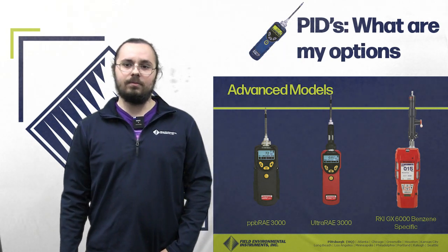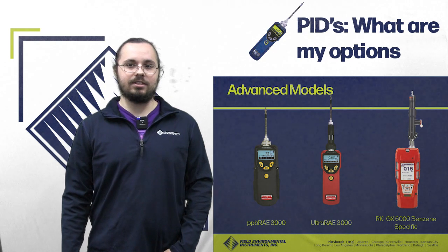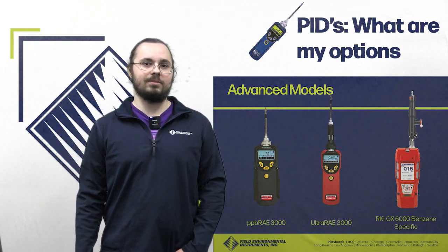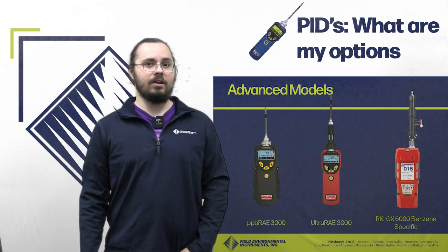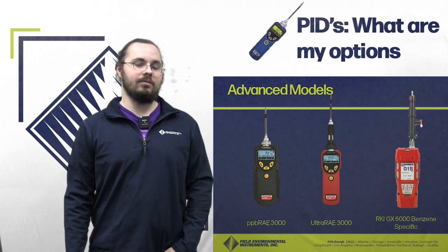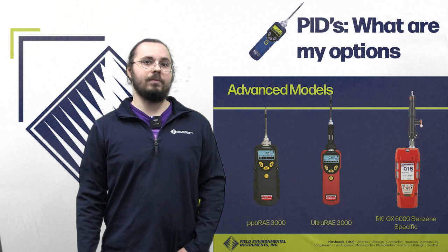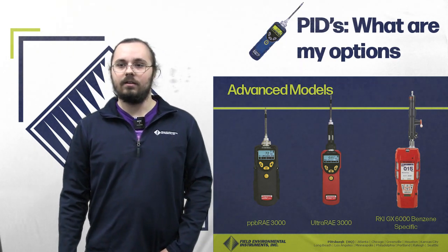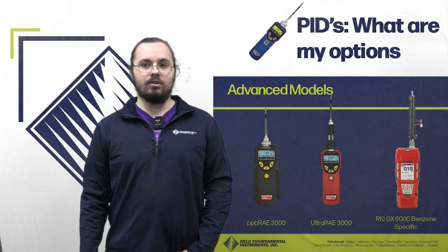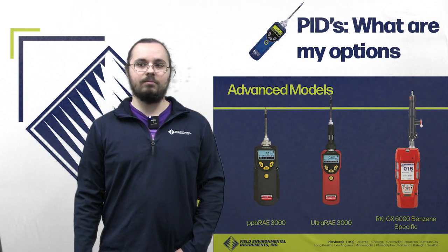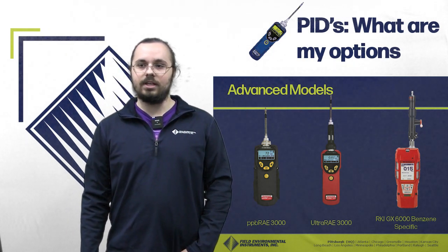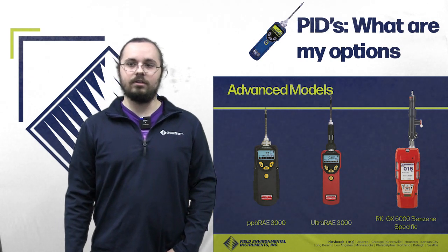Some of the more advanced models we carry here include the ppbRAE 3000, the UltraRAE 3000, and the RKI GX6000 benzene specific. The ppbRAE 3000 is very similar to the MiniRAE, except in this case it can measure up to parts per billion readings. It can read anywhere from 0 to 9,999 parts per billion and has a 10.6 eV lamp included.